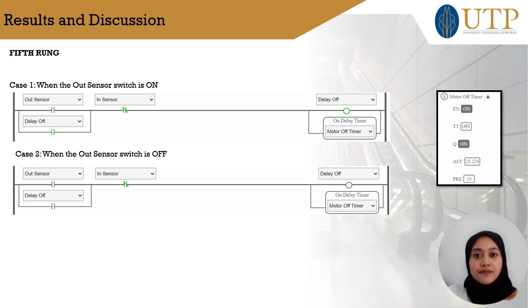The sixth rung is the continuation of the fifth rung. This is where the motor off timer switch from the timer in the fifth rung will trigger the output motor off. The normally open switch will be activated once the motor off timer has elapsed, passing the 25-second preset value. Once the motor off output is activated, the motor power will be cut off by the normally closed switch in the second rung. The motor, along with the other components, will be turned off, indicating no passenger on the escalator.